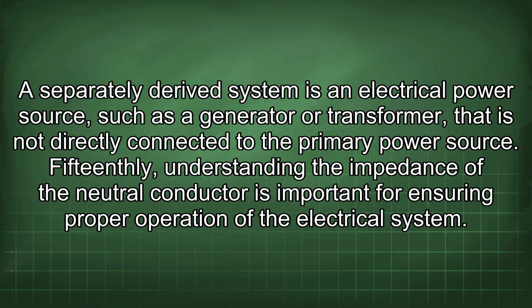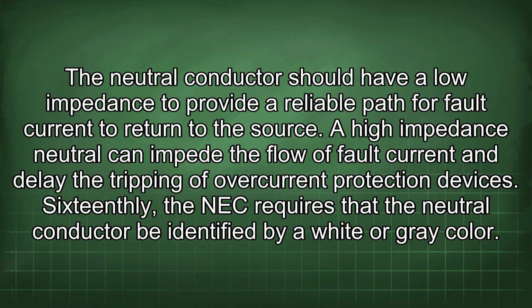15thly, understanding the impedance of the neutral conductor is important for ensuring proper operation of the electrical system. The neutral conductor should have a low impedance to provide a reliable path for fault current to return to the source. A high impedance neutral can impede the flow of fault current and delay the tripping of overcurrent protection devices.